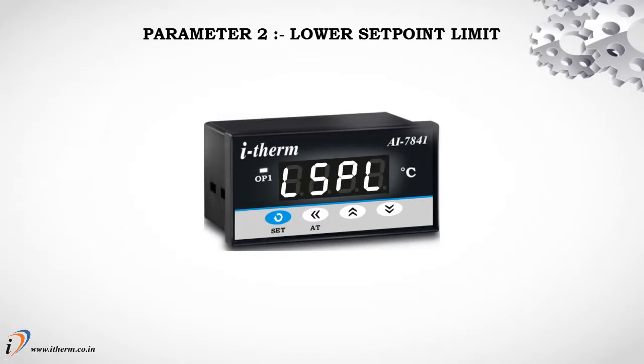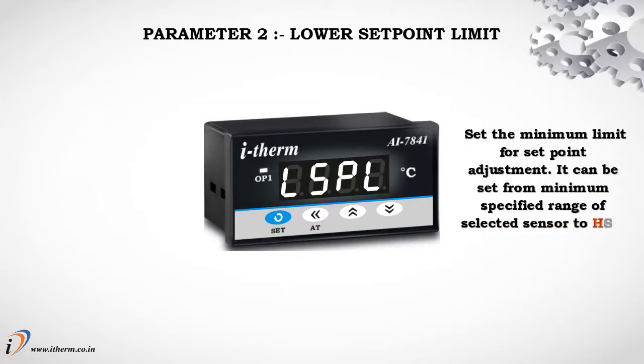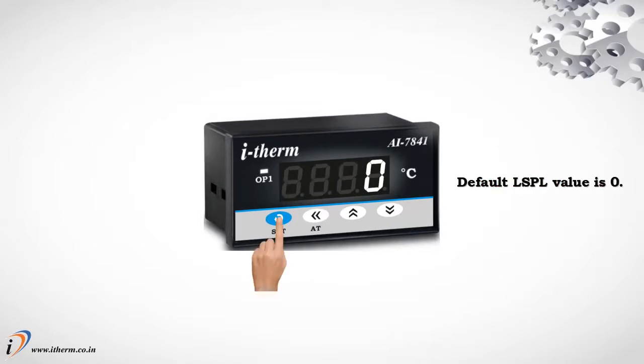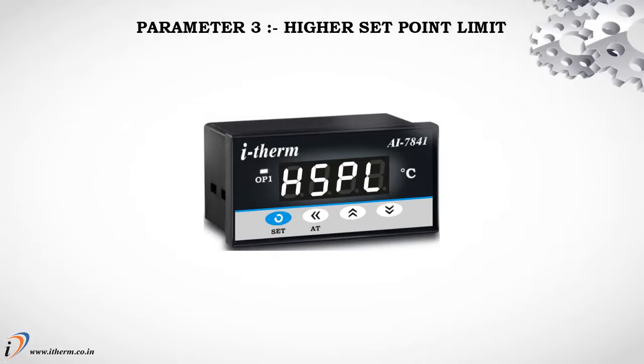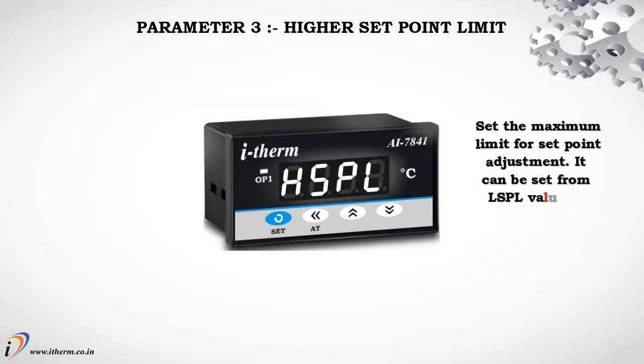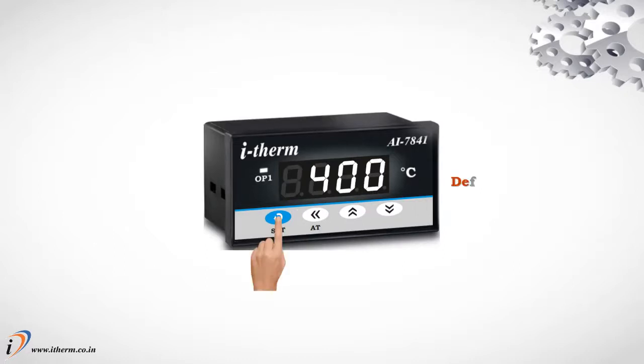Parameter 2, Lower set point limit. Set the minimum limit for set point adjustment. It can be set from minimum specified range of selected sensor to HSPL value. Default LSPL value is 0. Parameter 3, Higher set point limit. Set the maximum limit for set point adjustment. It can be set from LSPL value to maximum specified range of selected sensor. Default HSPL value is 400.